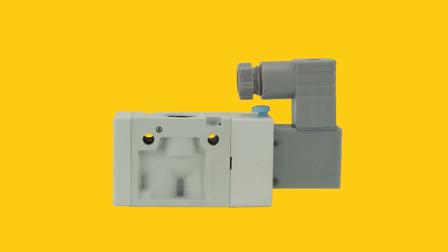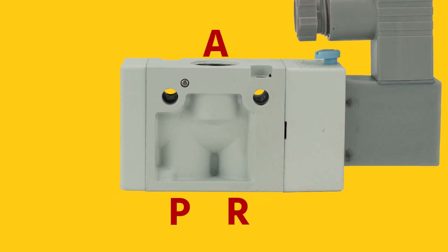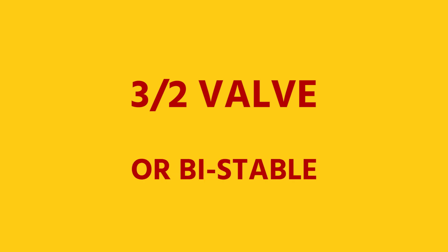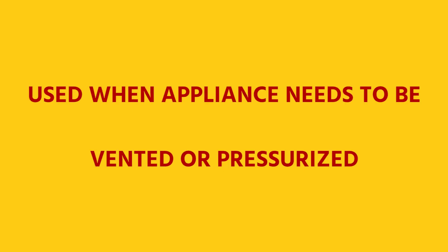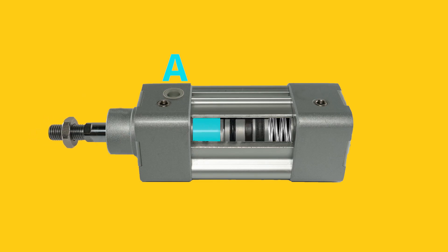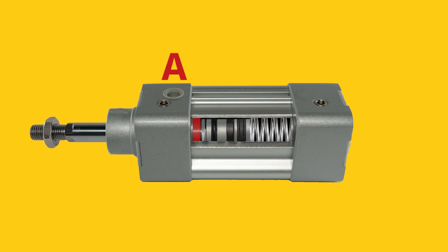A three/two-way valve has three ports and two states. These valves can be normally open, normally closed, or bistable. They are used when your appliance needs to be either vented or pressurized. An example is a single acting cylinder. The valve fills the cylinder through one port but also vents the cylinder afterwards through the same port to realize a new working stroke.